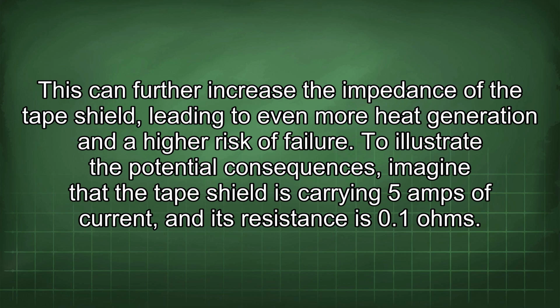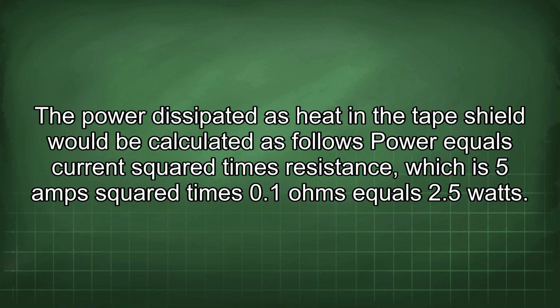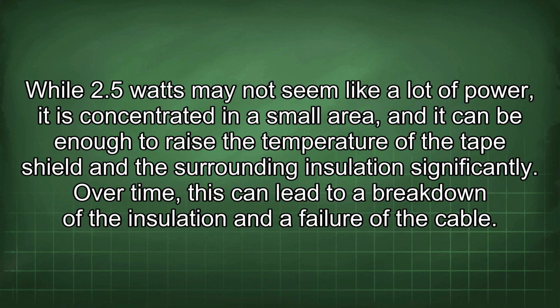To illustrate the potential consequences, imagine that the tape shield is carrying 5 amps of current, and its resistance is 0.1 ohms. The power dissipated as heat in the tape shield would be calculated as follows: power equals current squared times resistance, which is 5 amps squared times 0.1 ohms equals 2.5 watts. While 2.5 watts may not seem like a lot of power, it is concentrated in a small area, and it can be enough to raise the temperature of the tape shield and the surrounding insulation significantly. Over time, this can lead to a breakdown of the insulation and a failure of the cable.